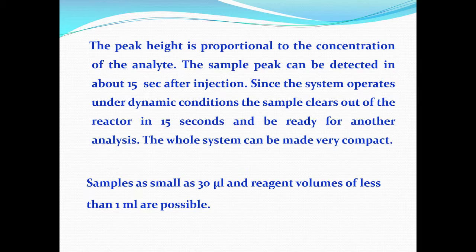Since the system operates under dynamic conditions, the sample clears out of the reactor in about 15 seconds and is ready for another injection. So, the whole system can be made very compact, and samples as small as 30 microliters and reagent volumes of less than 1 ml normally are possible to use.